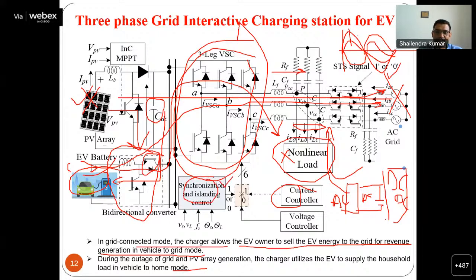Here we have implemented 3 controls: synchronization and islanding control, current control, and voltage control. The synchronization and islanding control monitors the grid parameters like grid voltage, load voltage, frequency, grid voltage theta, PCC voltage theta, and standalone theta. Once these are within limits, we can connect this converter with the grid. Otherwise, we are not allowed to connect the inverter with the utility grid, so the system operates in standalone mode.